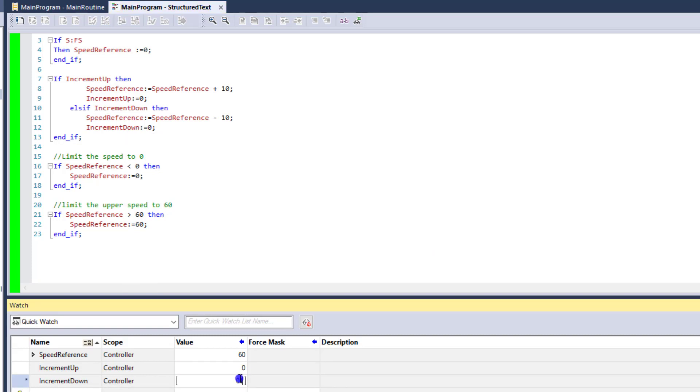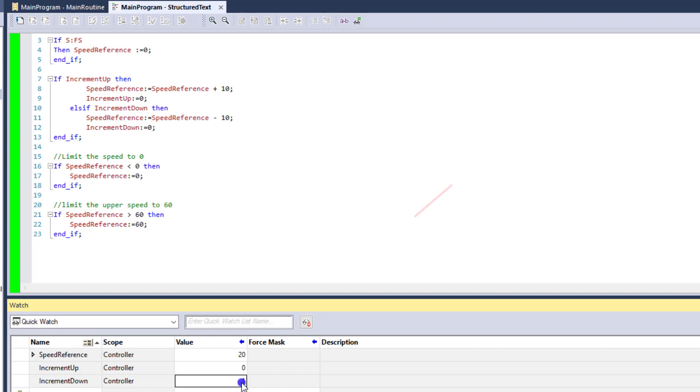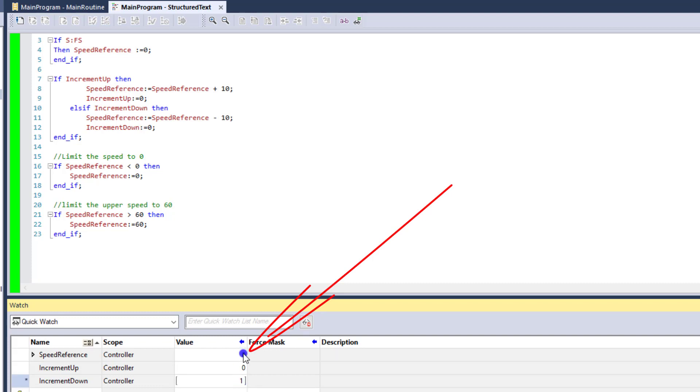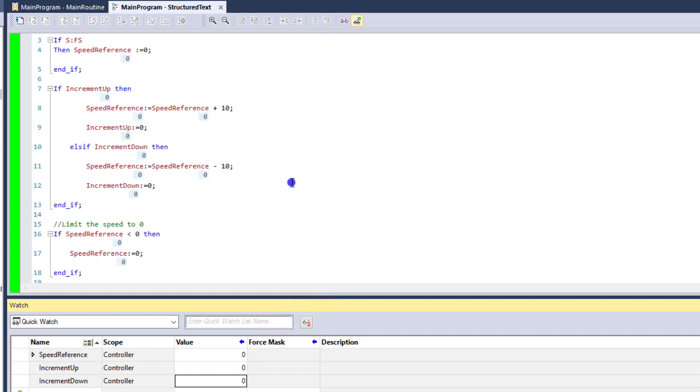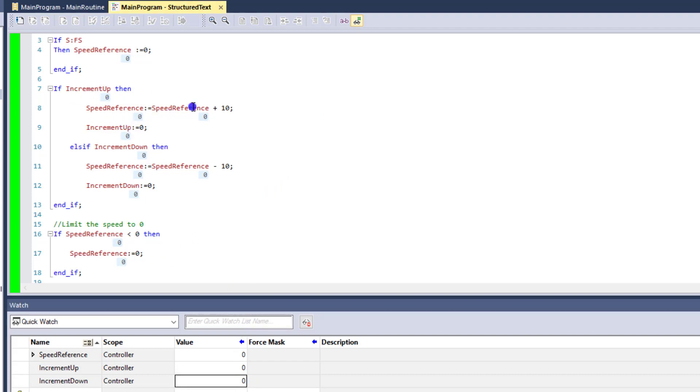So, let's just show you that same exact thing running down to below zero. Now, below zero, it will force a zero into the system so that we cannot run the motor backwards. So, if I were to index that down again, it's going to stay at zero. See, as you see right here, if it's less than zero, it's going to push a zero in there. So, the speed of the actual speed reference cannot go any lower than zero. And that's because of this logic right here.